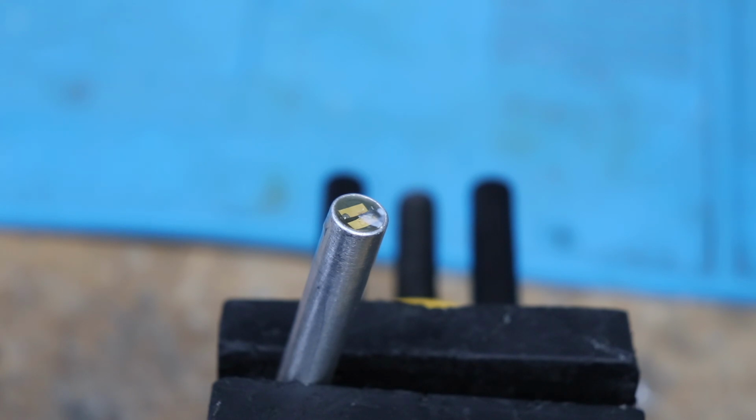The fetal Doppler machines are usually around 2 megs. The vascular probes do go up; I've got a machine here which goes up to about 9.4, 9.6 megs. Generally, the higher the frequency, the more superficial the vessels the probe tends to be used for. Other than that, there's not much to it. It basically has 2 coax cables with a couple of phono connectors on it, which plug into the Doppler machine, and that's it.